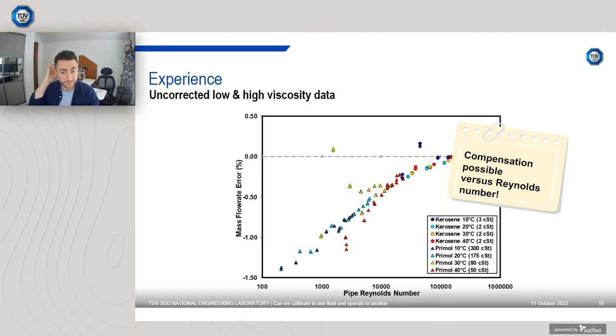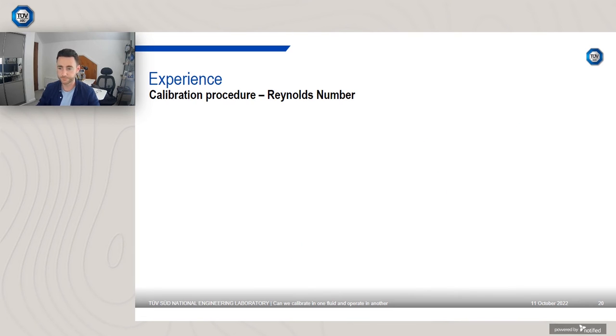So what does that mean for us with respect to the title of this webinar? Well, this means that if you can calibrate a Coriolis meter for high viscosity fluids with respect to Reynolds number, that means that you don't need to match viscosity. So you don't need to match the fluid perfectly. You can potentially use a substitute fluid at one or two temperatures. As long as you can cover the majority of the Reynolds number range, then you can potentially calibrate that meter with maybe a medium viscosity fluid, depending upon the temperature, and achieve the same Reynolds numbers depending upon the velocities that you can achieve in the laboratory. You could characterize it with respect to Reynolds number. So that's one method that you could use, and I've got some detailed steps here.